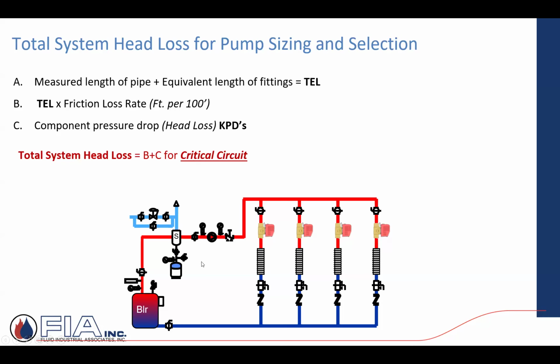So for the critical circuit they're referring to, in this case, again, all things being equal, I want to calculate the pressure drop of this guy. This is the furthest run. It's got the most amount of piping. It's going to offer the most amount of resistance. You can have scenarios where that doesn't hold true. I have 3 fan coils that all, say, have the same pressure drop, and a 4th one that, for whatever reason, is very small diameter, but it has extreme pressure drop. And it might not be the furthest one away. This becomes the boss then. I calculate that guy with the highest pressure drop. And if I have a pump head that can overcome that, then it can overcome the other 3 lesser pressure drop zones. So you just got to be aware.